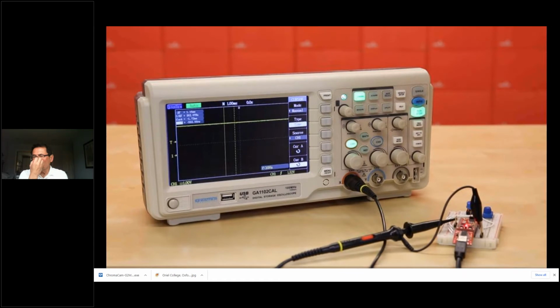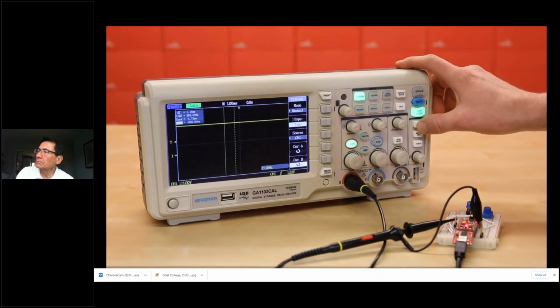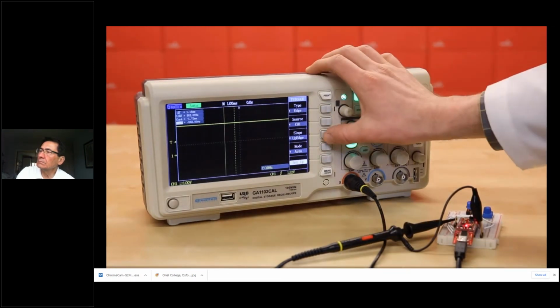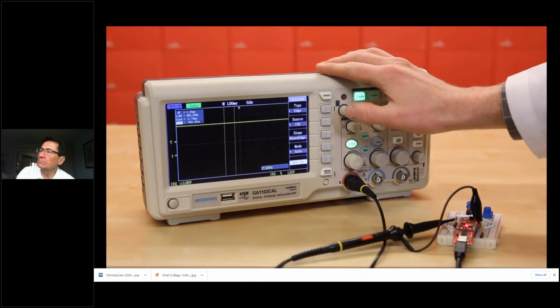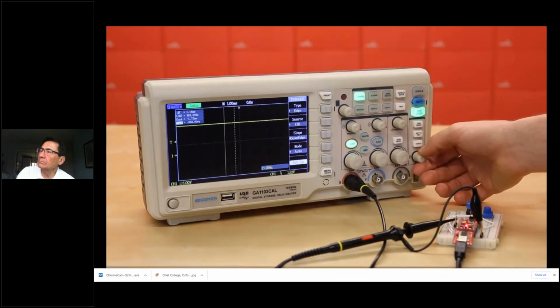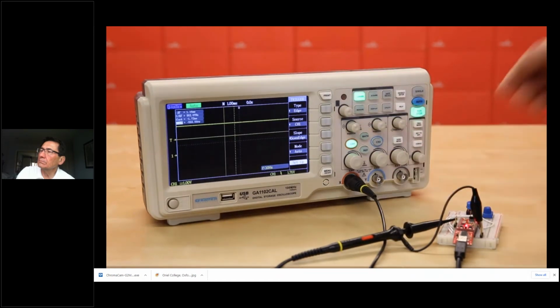Since it's not periodic, it's hard to capture in view, so we need to tell the scope to only perform a single sweep once it detects a rising or falling edge, and not keep sampling and drawing on the display. To do that, we first have to set our trigger to falling edge, since this line is normally high and driven low. Set the trigger level to something below the default high voltage. We'll set it to about half the voltage.